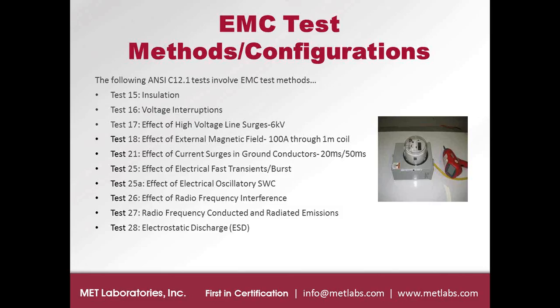The other test that is different in this spec is the current surge in ground conductor. Typically you may have come across surge testing, which simulates a lightning strike, done for any European testing. That test calls out a surge spec of 1.2 microseconds by 50 microseconds, wherein the first number is the rise time and the second number is the half time of the surge. This surge is different because it simulates a lightning strike to a ground rod nearby where the meter is situated. The rise time is a lot slower, 20 microseconds as opposed to 1.2 microseconds, as well as the test level: we are required to perform it at 20 kiloamps.